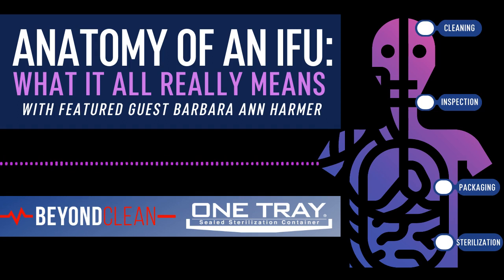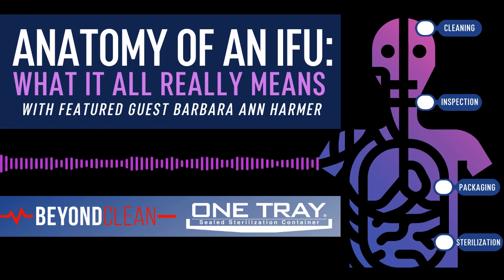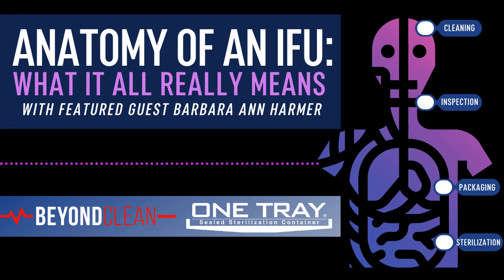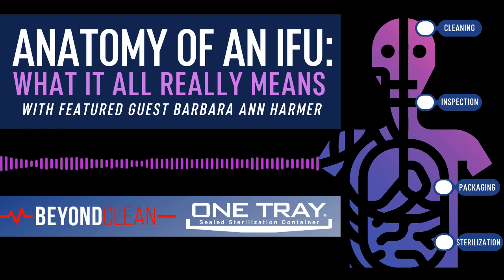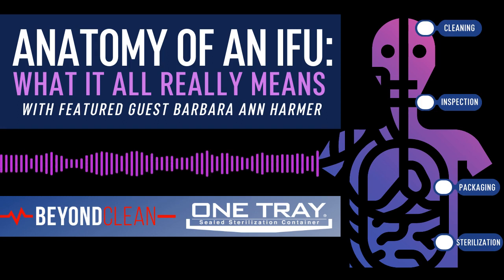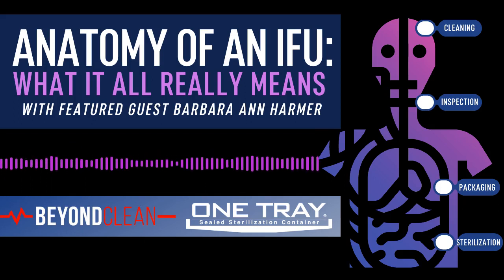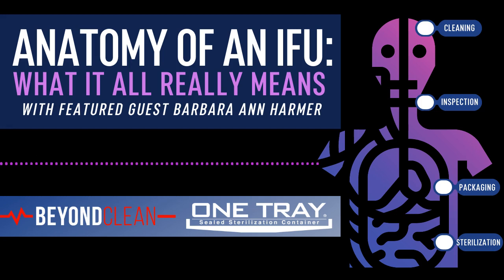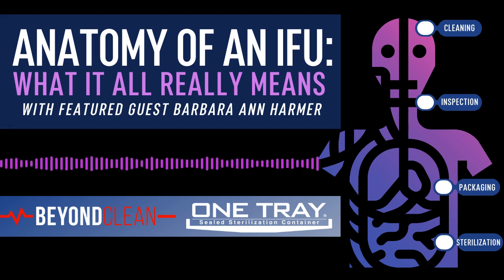That's why it's very important to look at the packaging system, because that's where dry time is coming from. It's the leg of the three-legged stool that gives you not only the dry time, but storage. That's really an important point. And so what you're telling me is that at the end of the day, just because an instrument or a device was validated in container A doesn't mean that you are then required to sterilize that instrument or device in container A. You still have options with packaging systems, correct? And that's what AAMI ST79 gives you in user verification and looking at product families, correct?